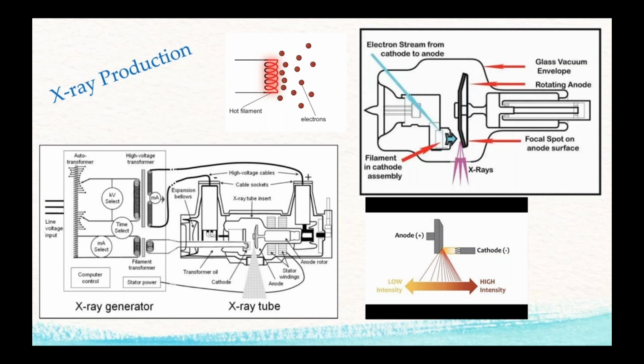Not going to spend a lot of time on the voltage, how we generate that, just the essence of time. But we have a low voltage section of an X-ray generator and a high voltage section of an X-ray generator. Low voltage, we usually save that for controlling the electronics that's going to produce our high voltage. So if you think about your kilovoltage, your kV, if you think about the tube current, which is different from running the current through the filament, we're talking about while we're making an exposure, there's current running through the X-ray tube itself when the electrons are going to hit the anode. That's called tube current. So that's called mA. When you hear the term mA, that's what that is.